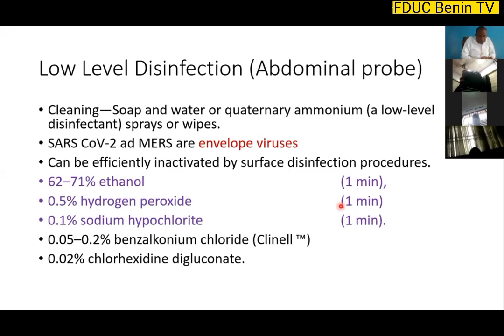Clinell wipes are available in Nigeria as well, so we can order these and use them for the abdominal probe. With a contact time as short as 1 minute, we are good and ready for the next patient. Vaginal probes must be covered before we use them, and after use, dispose of the sheet. But even after that, we need to do high-level disinfection, because if we remember the Spalding classification that I discussed earlier, the vaginal probe falls under semi-critical equipment.